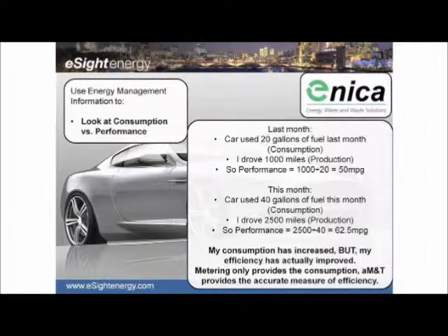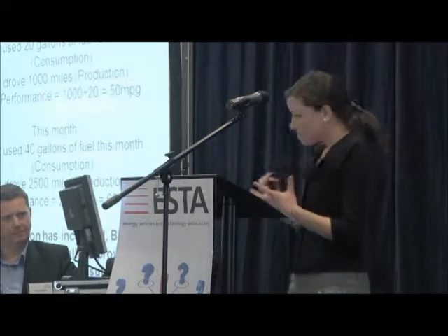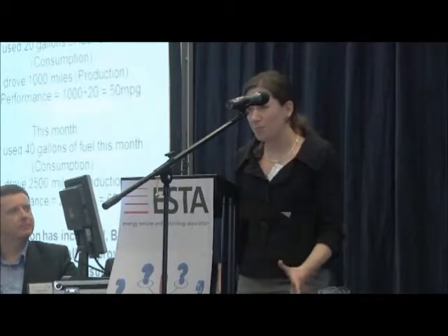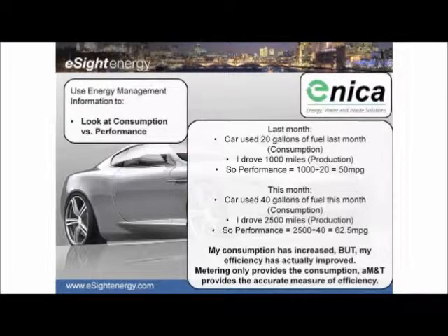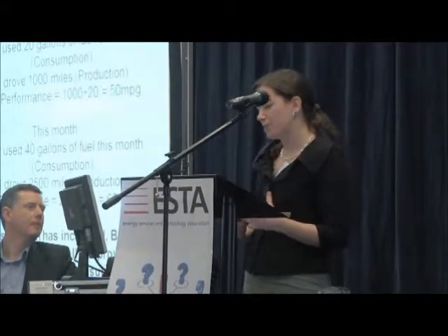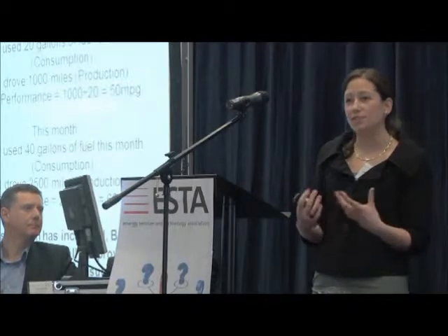Our next example comes from Enica, an energy consultant working in the UK. They've been working with AM&T to look at consumption against a driving factor so they can look at efficiency. For example, say I consumed 20 gallons of fuel last month but drove 1,000 miles — my performance is 50 miles per gallon. If this month my consumption doubled to 40 gallons but I drove 2,500 miles, my performance actually improved to 62.5 miles per gallon. So instantly looking at the figures you might think consumption has doubled — I've been bad — but when we look at efficiency, I've made an improvement. Metering alone can only provide consumption data, which is vital, but you need an AM&T system to compare that against a driving factor to look at efficiency effectively.